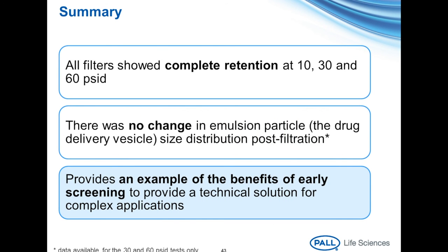In summary, we have shown an example of an early screen of a representative drug delivery vehicle using a single-pass small-volume challenge. All filters showed complete retention at 60, 30, and 10 PSID, and there was no change in emulsion particle size distribution. This early screen is a critical step, particularly in the development of a nanoemulsion drug delivery formulation and the evaluation of the proposed manufacturing process prior to finalization. It is very helpful when eventually moving towards successful validation of the final manufacturing process.